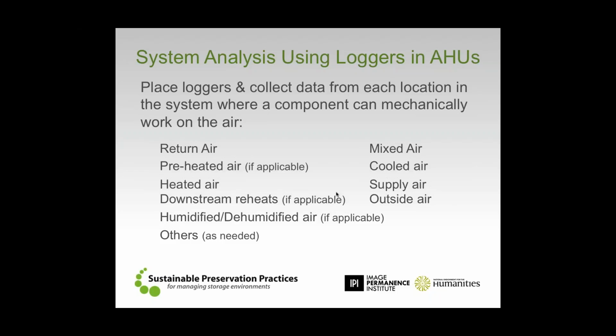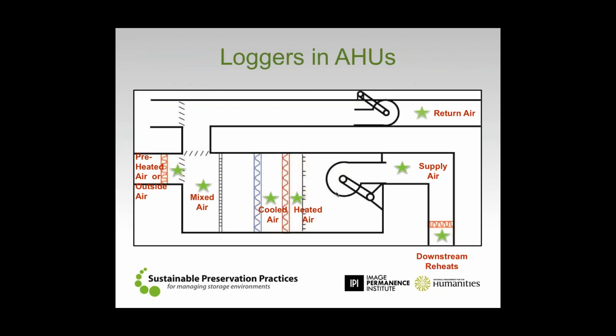We want to find out as we put a data logger in the return air and in the outside air blend, you know, when we start looking at the mixed air condition where those two air paths come together, how much outside air are we using and how much return air are we using? There are several different equations that you can run in order to find out what your balance is and find out if you're using more outside air than might be necessary. And at the same time, you want to know what that mixed air condition is as it moves through the filters. When it hits the cooling coil, how much work is that cooling coil actually doing? So we might want a data logger after the cooled air location as well.